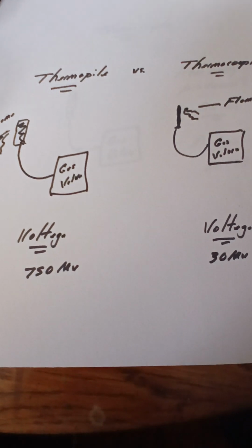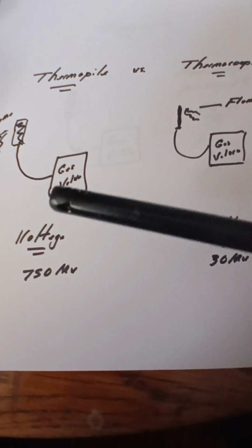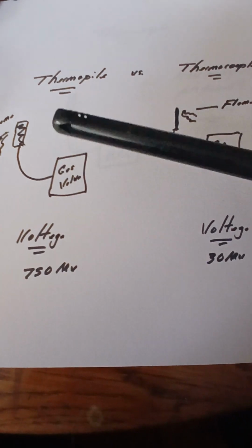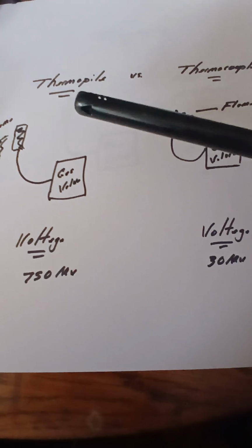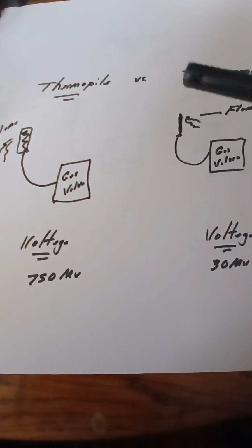And her question was very valid. So where are the batteries? Well, there are no batteries, or perhaps there may be or may not be, but generally speaking, they may not be. But this flame heats this up, creates 700 millivolts. This is a thermopile. Now, a thermopile, from my understanding, is a combination of several thermocouples.